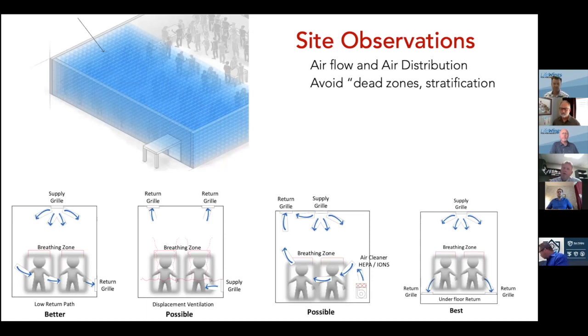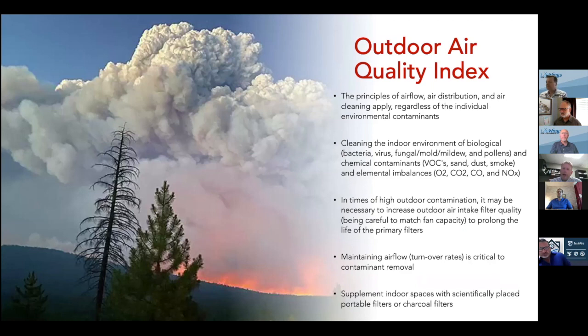What we've seen is districts opening outside air dampers in buildings. Obviously the heating or cooling season affects that, and smoke from wildfires affects that too. But we also see a lot of these units don't have pre-filters, or the outside air mesh filter is so damaged that contamination from outdoors is just plugging your filters immediately. Some of those photos on the filter slide showed filters only a month old, and there's so much contamination in the air right now that opening outside air dampers just makes that worse. So bringing in as much outside air as possible isn't necessarily the best scenario, because energy efficiency is affected, and your filter change frequency is affected for each season.